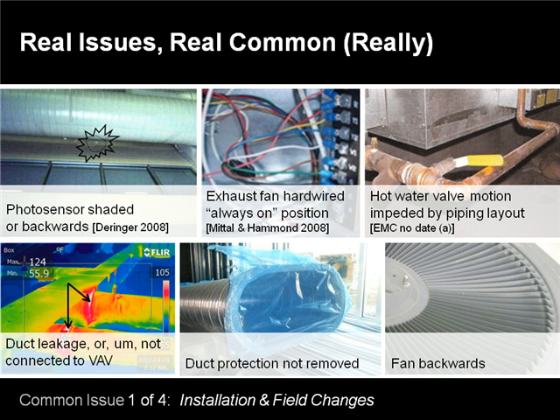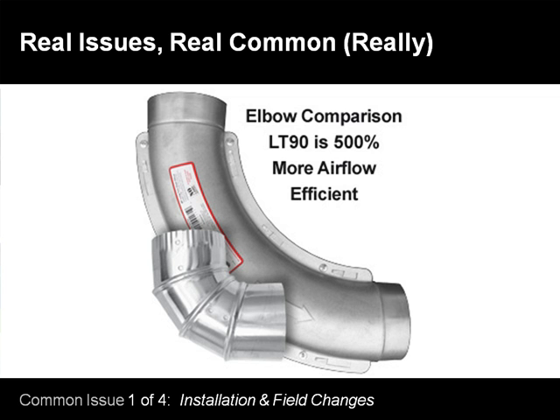And then we've also had fans running backwards. Sometimes we'll see linkages that are never even hooked up on valves and dampers, and that's pretty much what we got on that one. There's a lot of other ones, I just picked some of the top ones. And then another thing that we see common in the field, we'll see a contractor who decides, why buy that big expensive long radius elbow when I can get short ones for a quarter of the price? And he goes and installs all these different duct connections that are not what was specified or what was in the design intent.